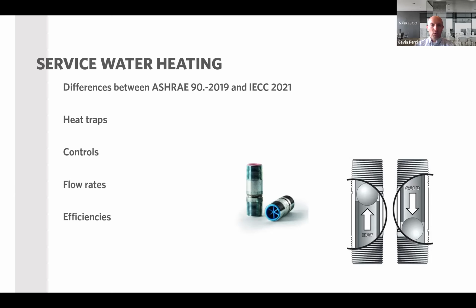These are all controls. If you want to think about it, you're going to have a control. The easiest way to think about it is you're going to have a control system no matter what on your service water heating, no matter which pathway. The way that those are controlled could be very well different depending on the pathway you go down. But you still need to have some type of control system on there. So from a price standpoint, it's probably no different. You're still buying a control package, but from a functional testing and commissioning standpoint, which you have to do, there are some differences in terms of what needs to be checked out.